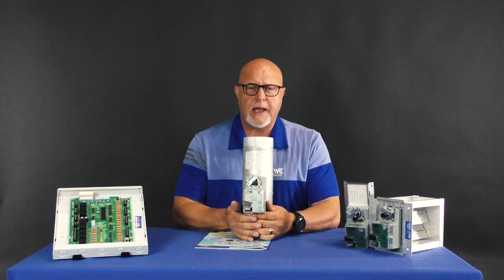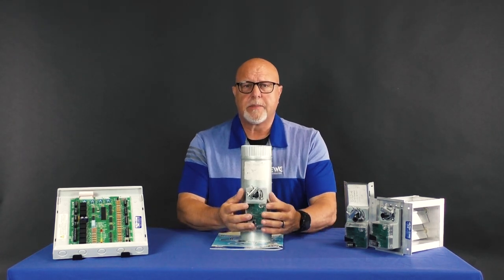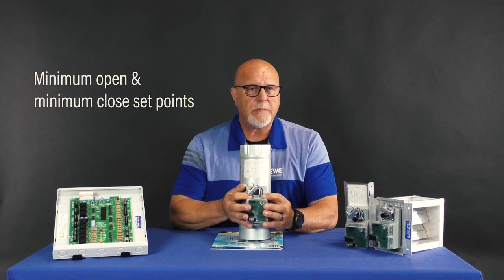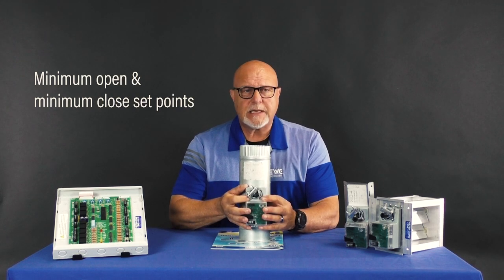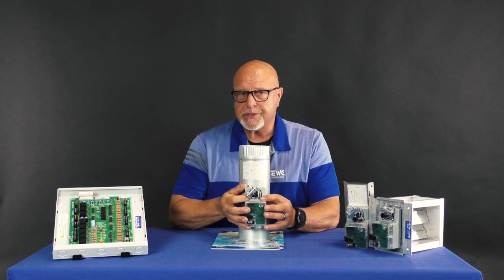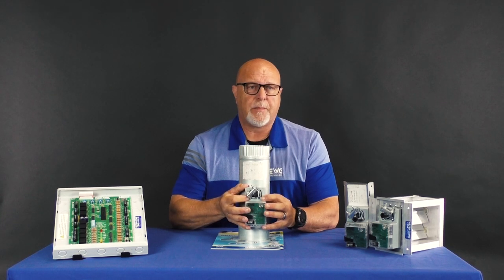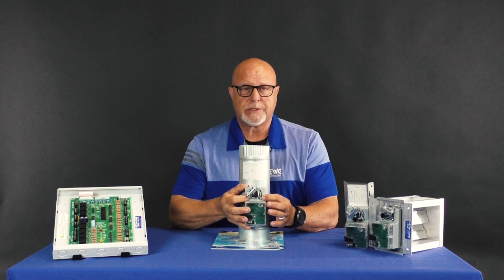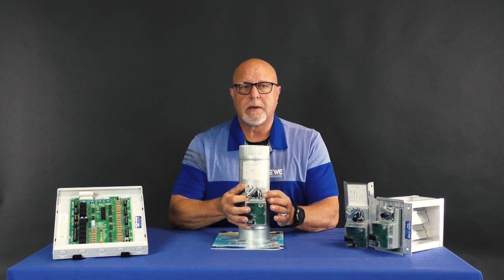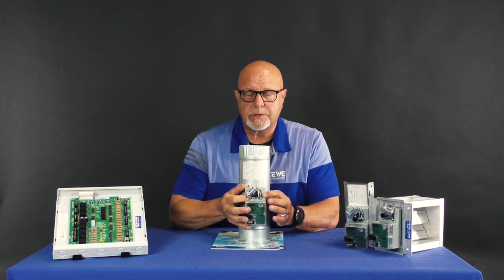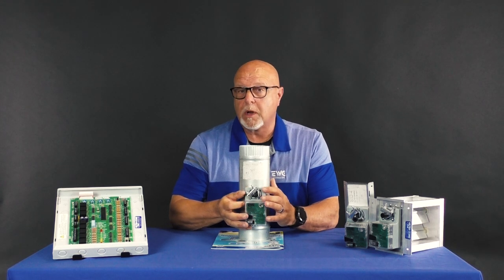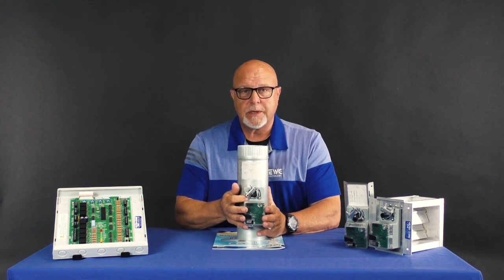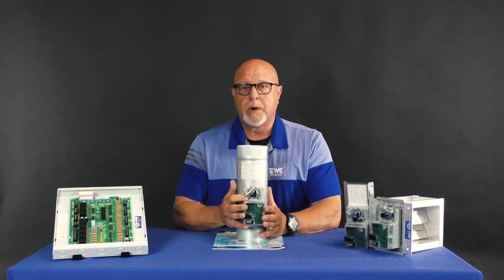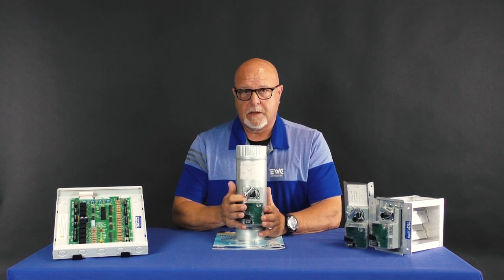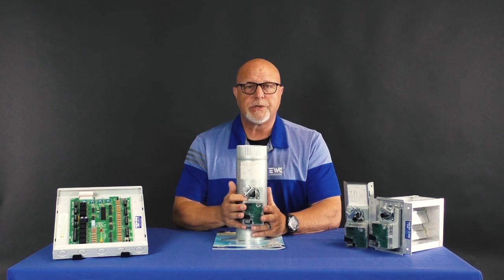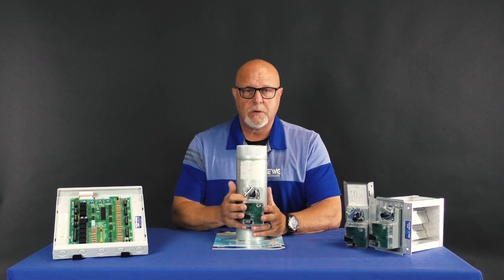One of the other features that contractors really love about our dampers are the minimum open and minimum close set points. This is basically making our damper, in addition to a zone damper, a balancing damper. I can move this screw to a certain point and restrict the damper to close a certain amount, meaning it won't close all the way. I can also move this one, the minimum open, to where it won't open up all the way. It's a very nice feature. Most of my competition only give you the minimum close position.